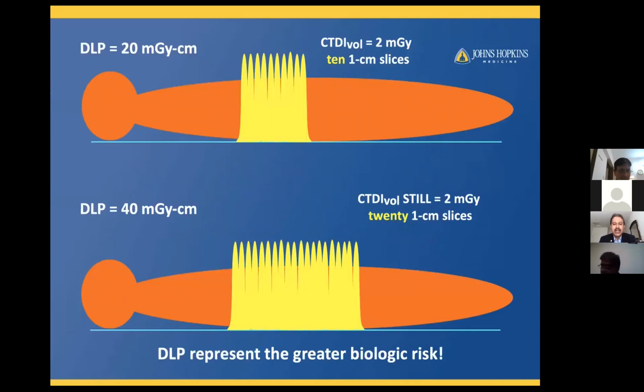There are two scenarios here. If the same techniques are used between two patients, then the CTDI volume in these two cases will be the same, 2 milligray. The first case has 10 slices of 1 centimeter, and the second one has 20 slices of 1 centimeter. Therefore, because of the scan length, the DLP in the second case is twice that of the first case. And that's important for understanding biological risk estimation and so forth.